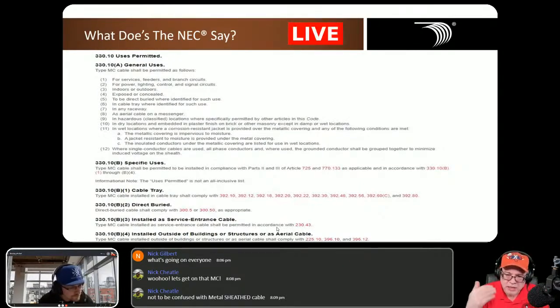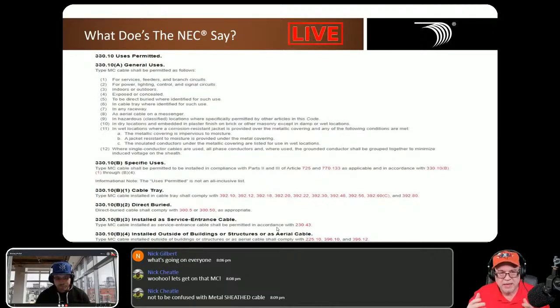So we're going to look at each one of these, but when I usually discuss it as a 30,000-foot view, Jay, I like to discuss what this means when you crack your code book open and you see this usage permitted and you see that it's broken down into an A and a B. So I like to explain it. And I always do it backwards because I'm going to explain B in all these specific uses before we explain the general use. So 330.10b specific use says type MC cable shall be permitted to be installed in compliance with parts 2 and part 3 of Article 725, which again is signaling and control, and 770.133, which is fiber optic, as applicable, and in accordance with 330.10b1 through b4.